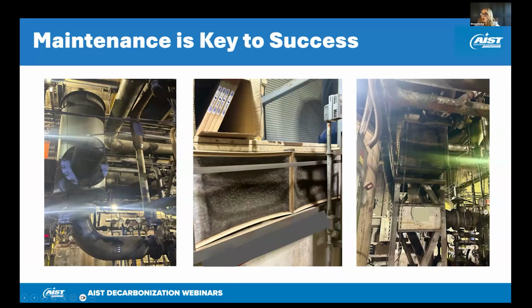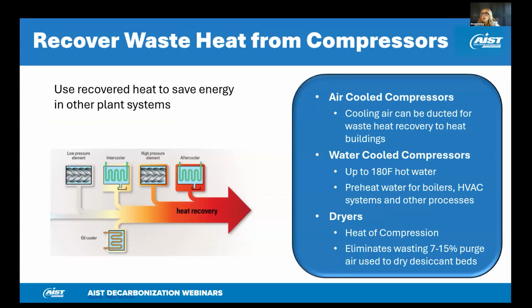Filtration is one of the biggest components that we find could be maintained better to alleviate issues with performance, reduce the power consumption of the system, and improve reliability. These filters here were so clogged with dust, dirt, and debris that they were actually bending the metal frame of the elements. What's interesting about this picture in the middle is that the new elements were sitting right on top of the compressor. So they were just in need of attention. A proper maintenance program that's scheduled with spare parts on hand goes a long way for reliability and reduction in power.